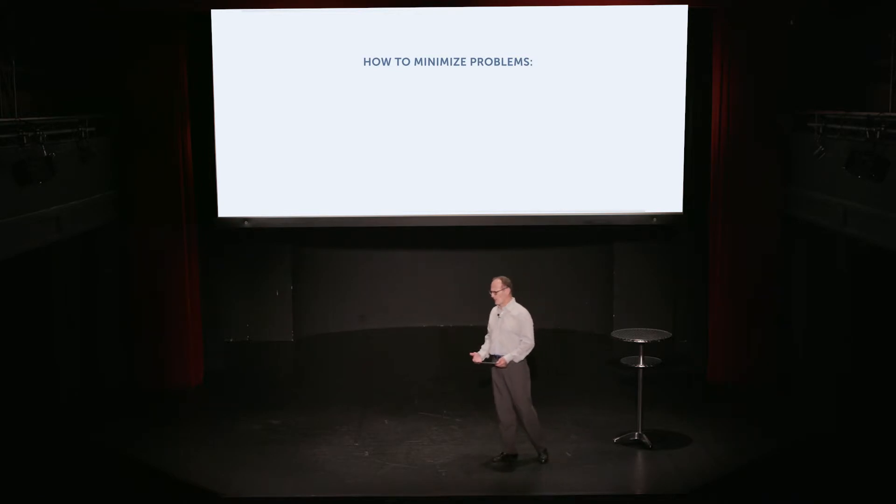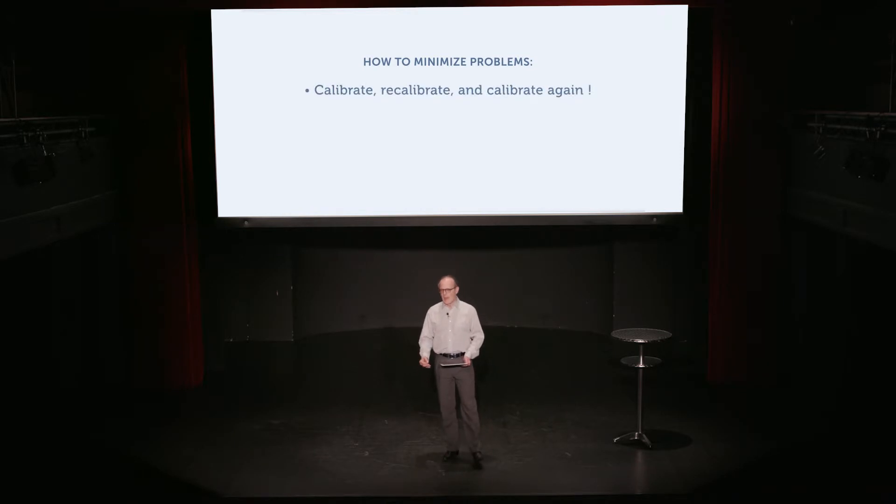Now, to take care of most of these, the most important thing is to calibrate. And for a simple calibration, if all you want to do is a gain-offset kind of calibration, two or three points at the extremities and at zero, for example, are sufficient. But if you want to correct for the non-linearity, then you may need to take many, many more points.